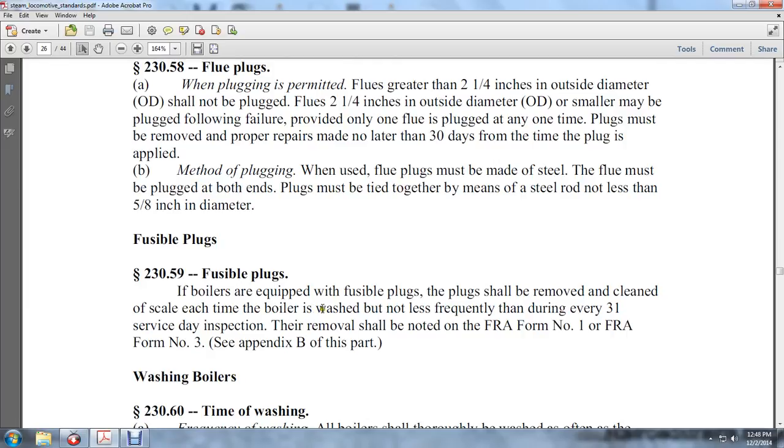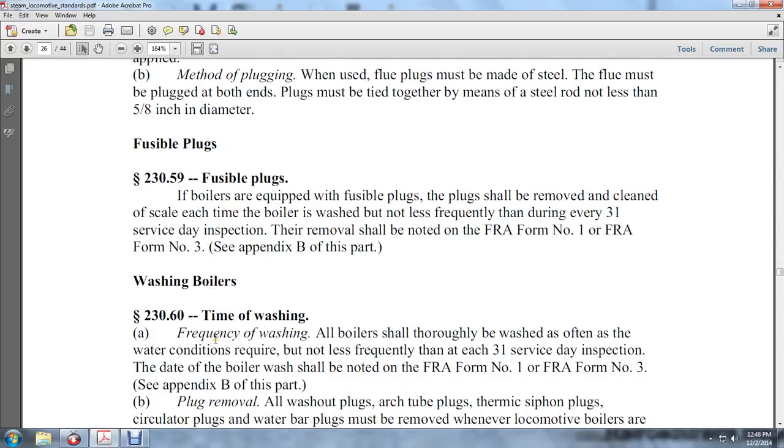Fusible plugs: For boilers equipped with fusible plugs, the plug shall be removed and cleaned of scale at each boiler washout, but not less frequently than every 31 service days. This removal shall be noted on FRA Form Number 1 or FRA Form Number 3. See the appendix of this report. Boiler washing: wash the boiler accordingly.